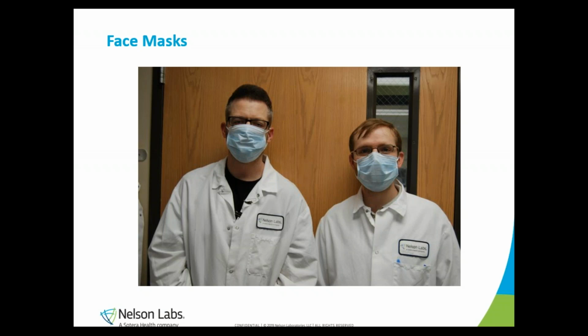Medical face masks are designed to protect others from wearer-generated aerosols. This helps prevent the spread of airborne diseases and helps maintain a clean environment in the surgical suite. As they are designed to protect the environment, the inside is the default test site for most of the testing. There is one test that is meant to evaluate how well the mask protects the wearer, and in this testing, the outside is the test area or the test side.